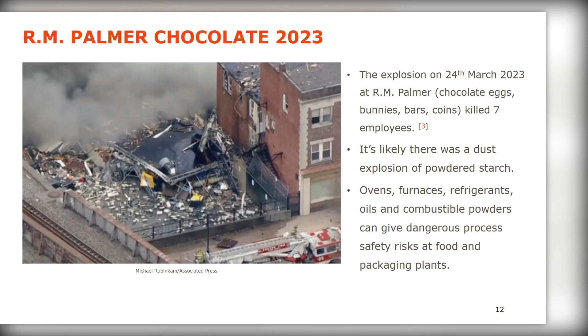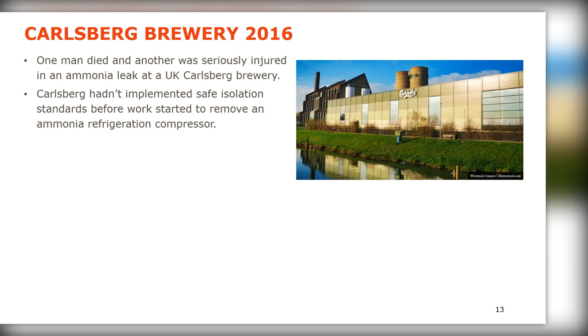My last example - again not particularly MOC, but just to show the breadth of process safety problems there can be - this was at a brewery in 2016. This was a death, or deaths, from an ammonia leak, because when they wanted to remove an ammonia refrigeration compressor, they hadn't implemented safe isolation standards.